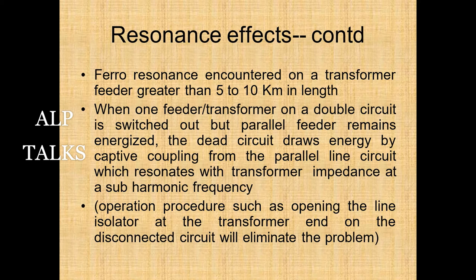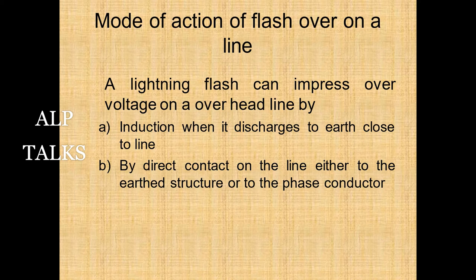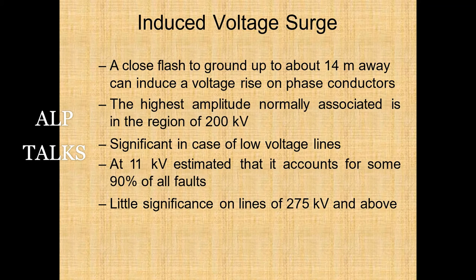A lightning flash can impress overvoltage on a line by induction when it discharges to earth close to the line, or by direct contact either to the earth structure or to the phase conductor. A close flash approximately 14 meters away can induce a voltage rise on phase conductors; the highest amplitude normally associated is around 200 kV. This is significant for low-voltage lines at 11 kV — estimated to account for almost 90% of all faults — but has little significance on lines of 275 kV and above.